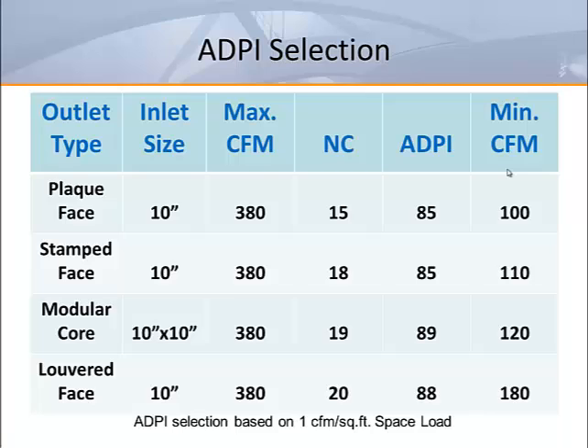The plaque face at design CFM is NC 15 and ADPI of 85. The unit will turn down to a minimum CFM of 100 and maintain an ADPI of 80 or greater. The stamp face is comparable with an NC of 18, an ADPI of 85, and a turn down to 110 CFM. The modular core is a bit noisier at NC 19, perhaps 20 with a 10-inch round adapter, but excels with an ADPI of 89. The minimum CFM turn down is 120 CFM. The louver face does well at NC 20 and an ADPI of 88, but is less flexible with a minimum turn down of 180 CFM.